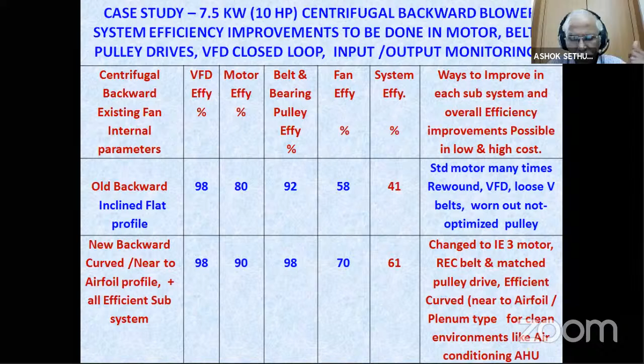You take a typical case of either a cycle pump when you are pumping your cycle, or a typical 5 HP blower. What is delivered is 3.7 kilowatt electrical power, but with the motor loss, the drive loss, and the fan loss, what is the air power delivered at the output? It is only 2.2 kilowatt. Almost 60% of the input power is used as output. 40% is gone, almost 1.5 kilowatt. It is going as heat.